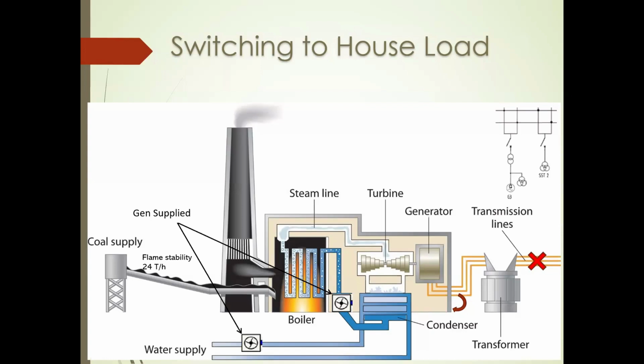Now, unfortunately, in the situation of under frequency of the grid, definitely the unit has to be tripped, resulting in the loss of all the 6 kV auxiliary power. So in an under frequency situation, these two items and their auxiliaries will trip. Therefore, both the rupture disk failure and the drum starving will occur. Hence, the tripped units will have no choice but to wait until the necessary equipment cools down. So 4-5 days have to be waited.